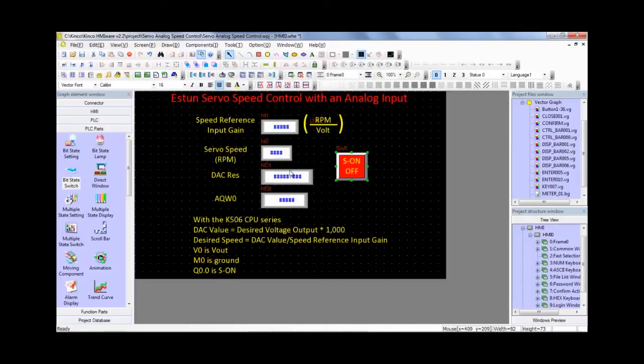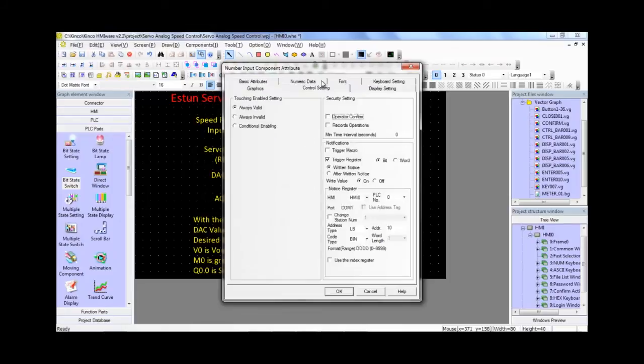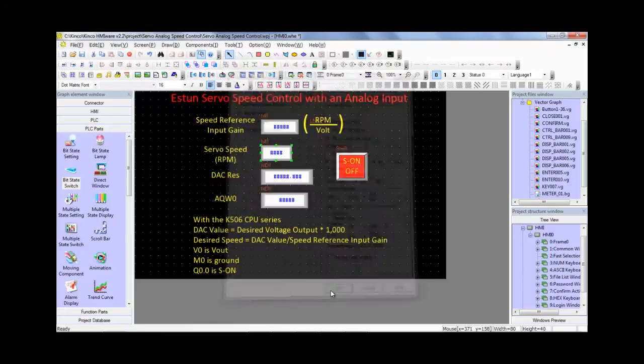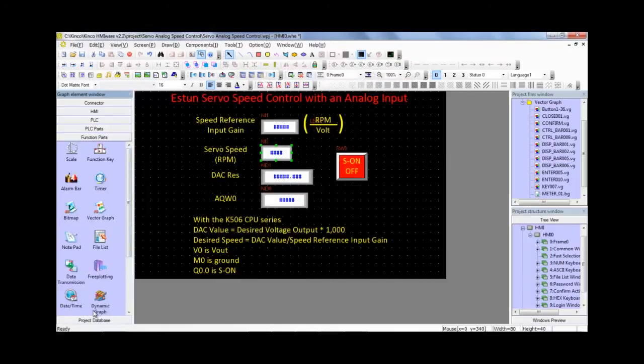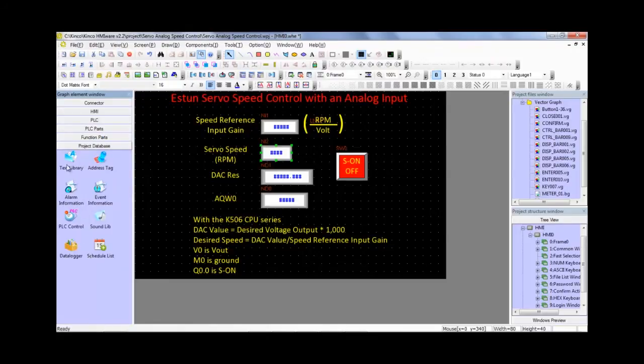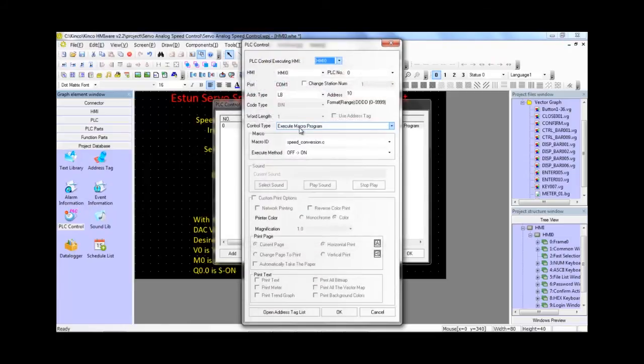And then the servo speed here, it's a local word register of 100. So this just stays here. But what this does when after we're done entering the speed that we would like, we go ahead and trigger LB10. And I've gone ahead and used the PLC function or PLC control function to make LB10 as a trigger to execute a macro program, speedconversion.c. So let's go ahead and open that up and see what that does.